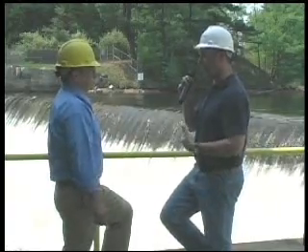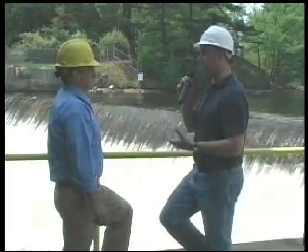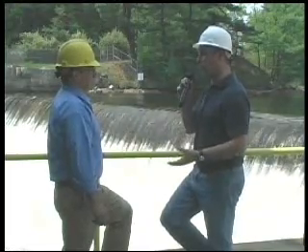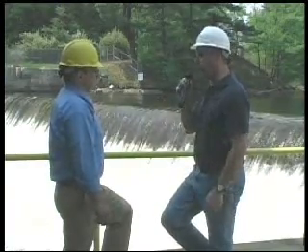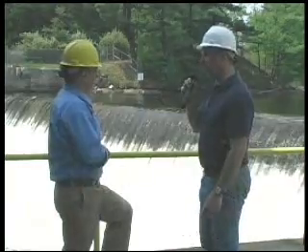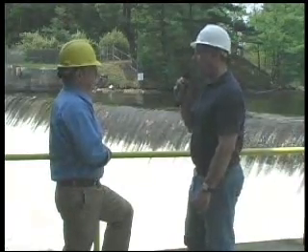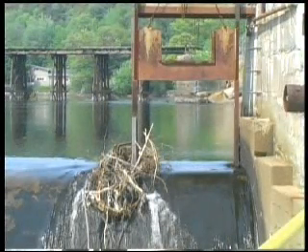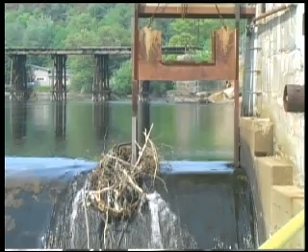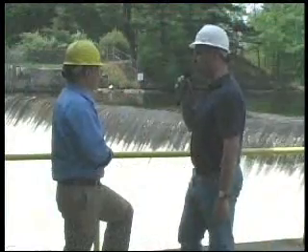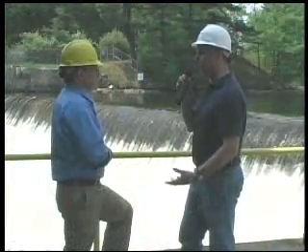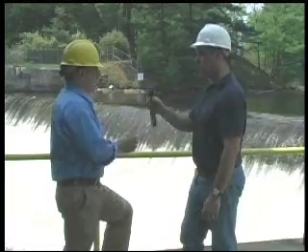Essentially, what comes down, whether it's by release from the Corps or unregulated stream flow from rainfall, is distributed over the spillway. One other feature I forgot to mention to you on the spillway is that we do have a notch gate that's essentially an extension of the flashboards. During normal season, we pass a certain amount of flow over there for downstream fish passage. During flood events, we raise that so it will react similar to a flashboard.